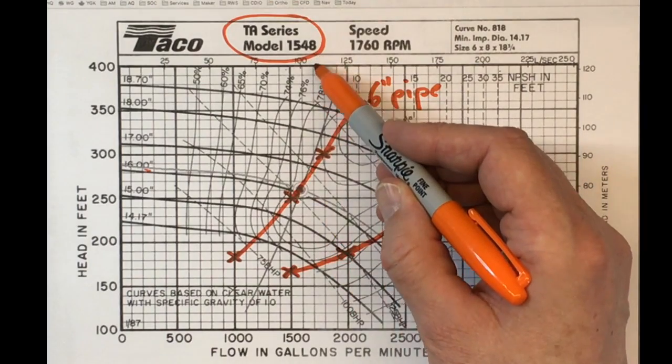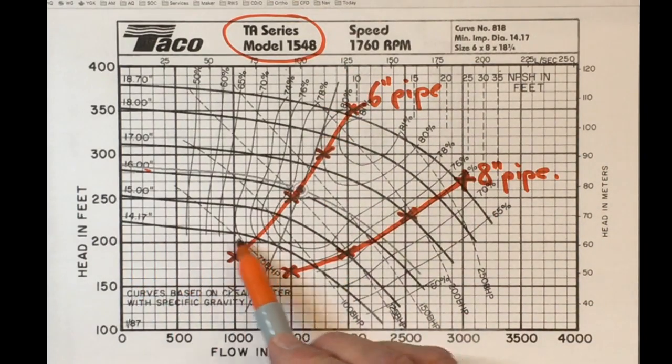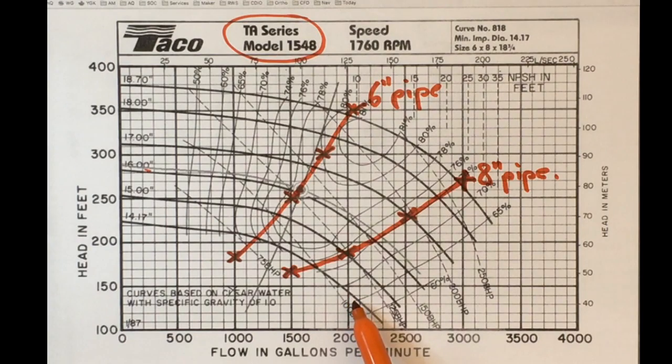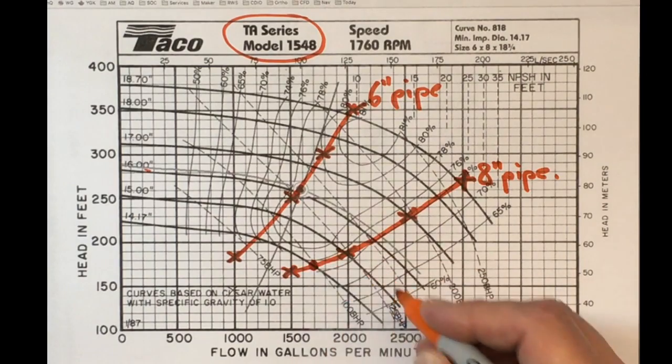I'd still be delivering more than the design flow rate if I just got the 14.17-inch impeller and installed it.